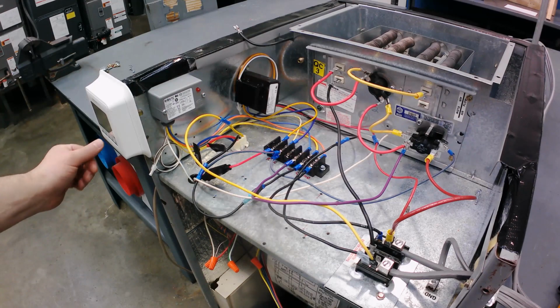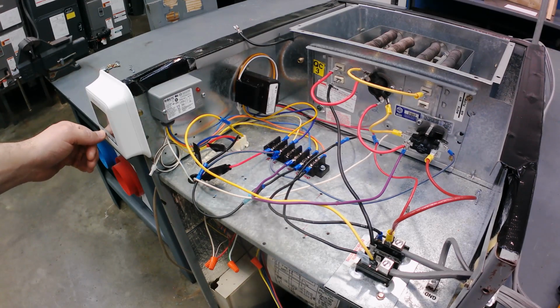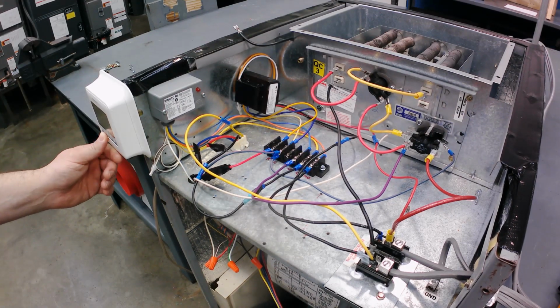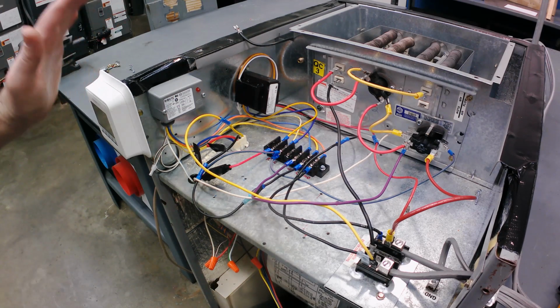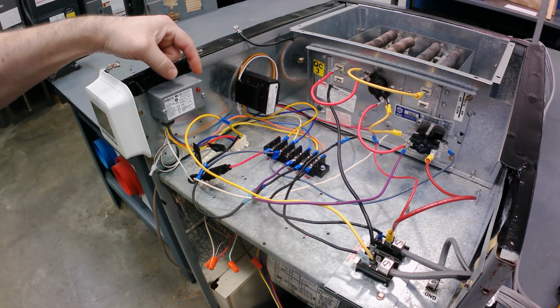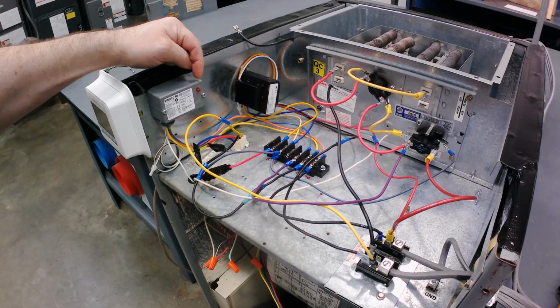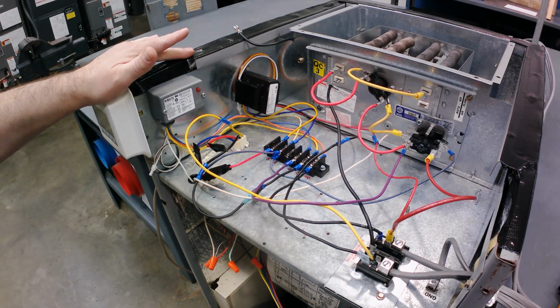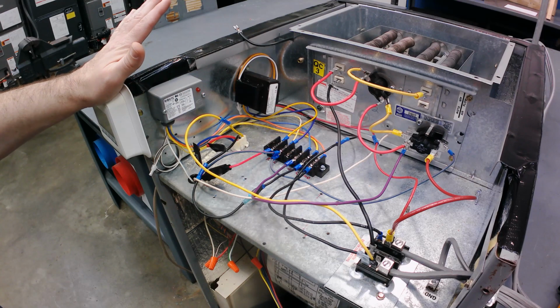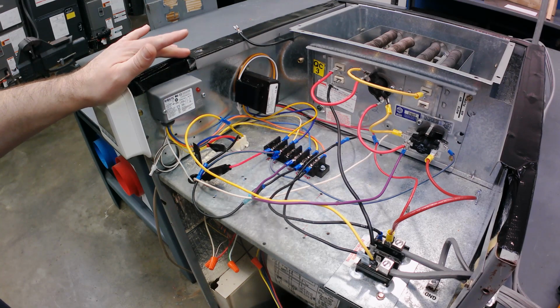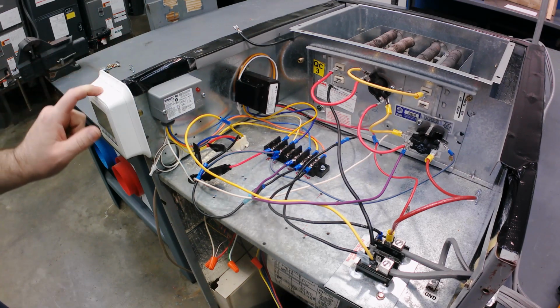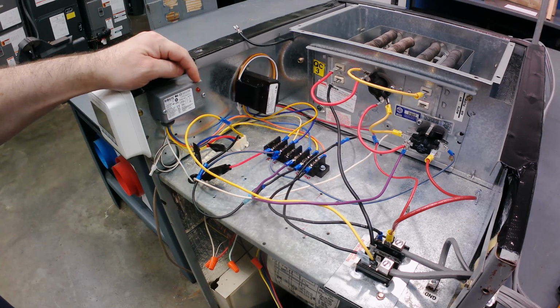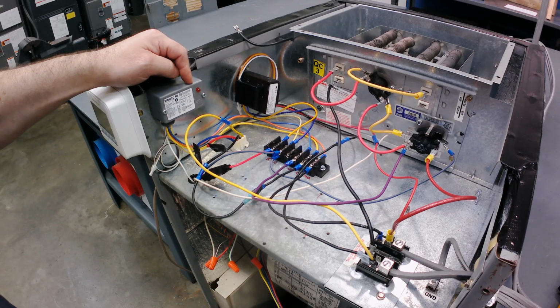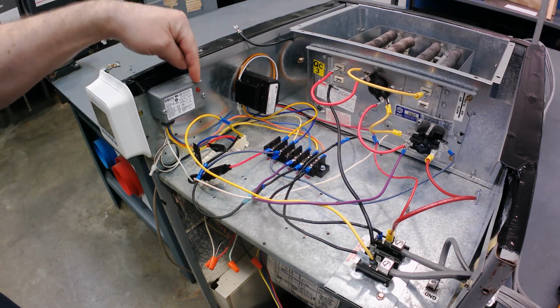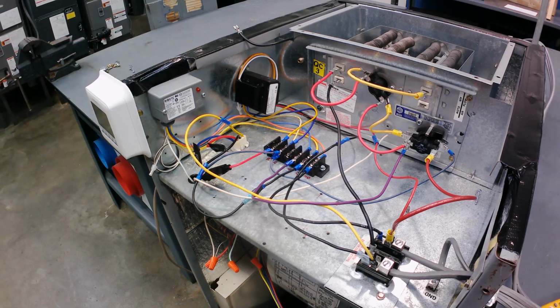Alright, so what I'm going to do here is turn on the system in heat, and this is an electric setup. So basically what I'm going to show you is that this relay, that LED only comes on when the coil is energized. I've got the thermostat set so that the equipment controls the fan, not the thermostat. So there's not going to be a call on the G circuit here, and that means this little LED is not going to get turned on because there's no 24 volts on the coil. So you can see here the light is off.